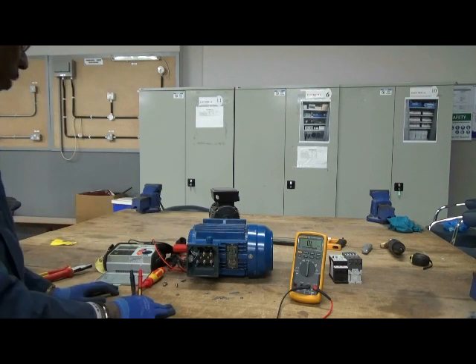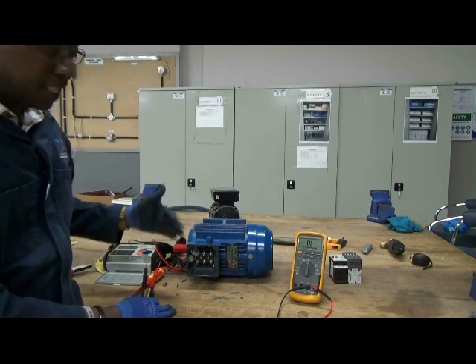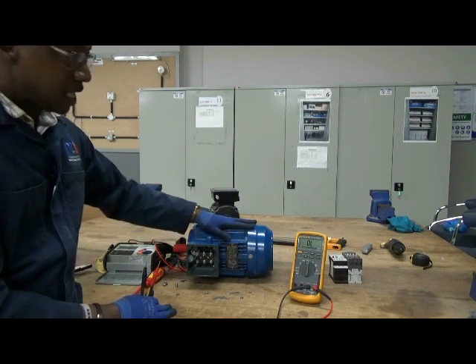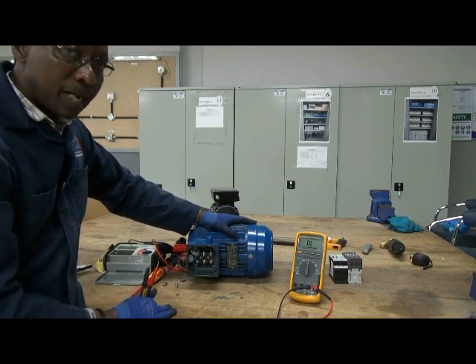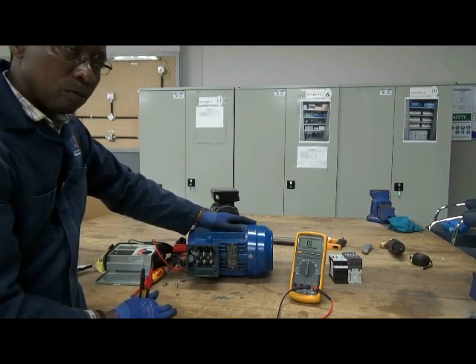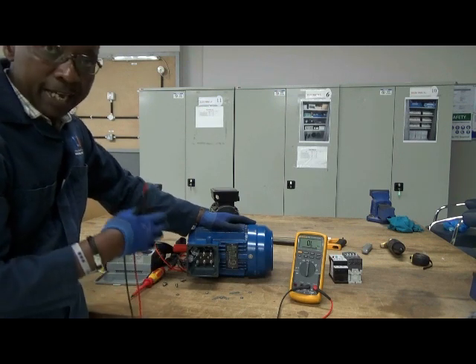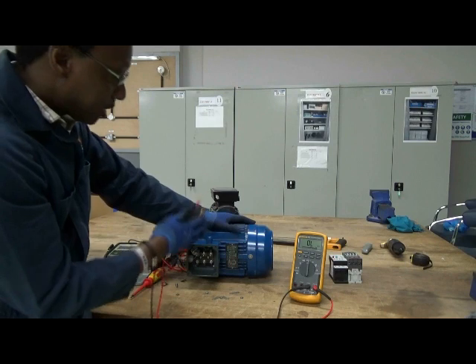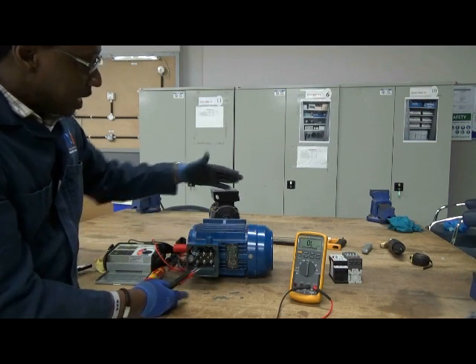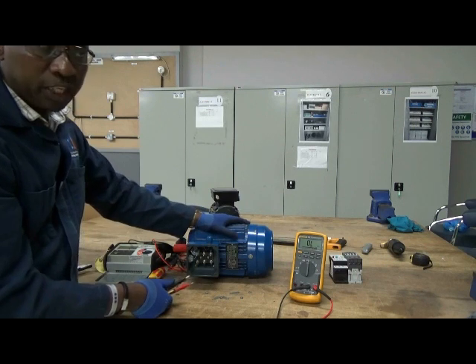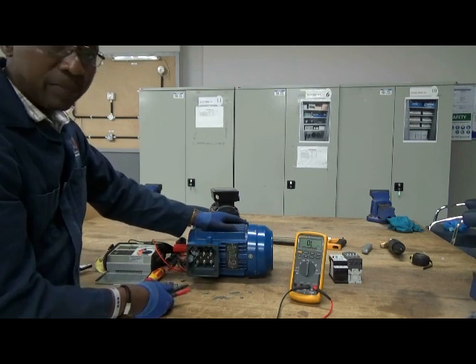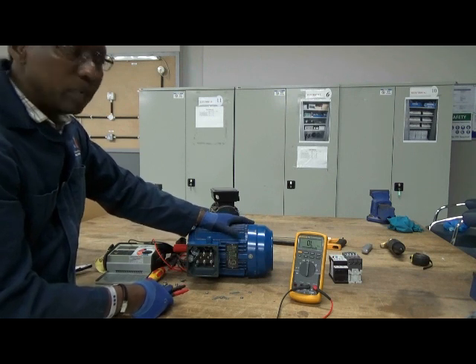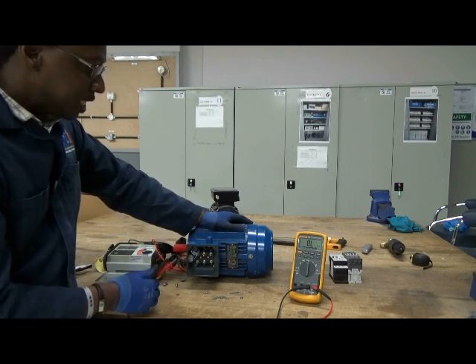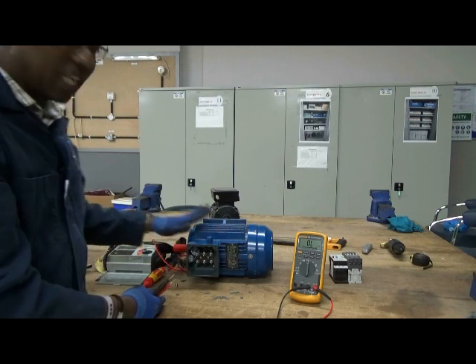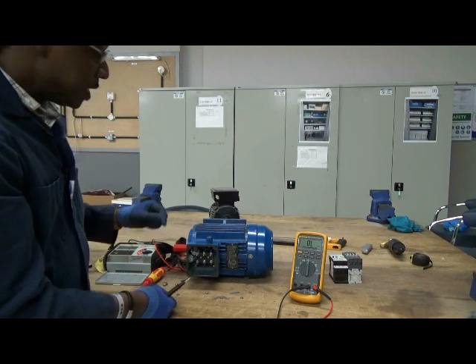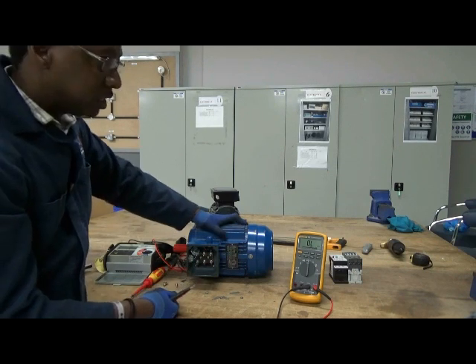So that is the resistance of the windings. I've basically determined that the three windings that are wound on this motor are balanced, and they are 3.1 ohms each. But I'm not sure whether the three windings are touching each other inside or are touching the body of the machine. And that brings me to the next test which I must carry out. This test is called the insulation resistance test. I will be testing that the windings are not touching each other inside, or that individual windings are not touching the body of the machine.